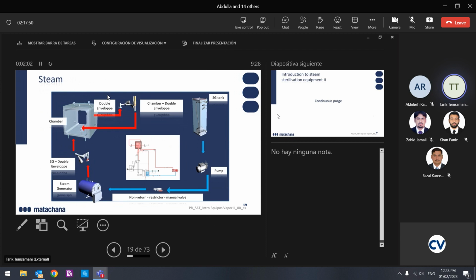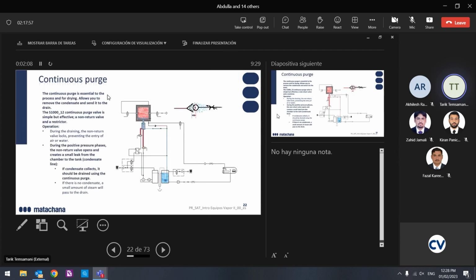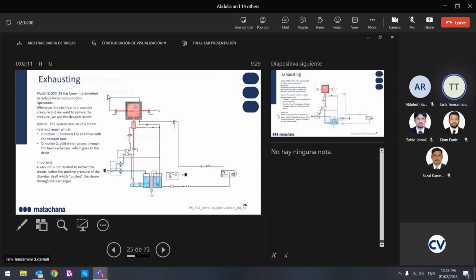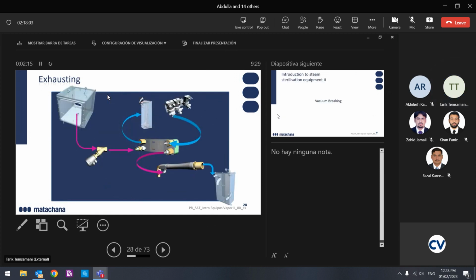But from the other side, we have the other line. I will explain better. Look, everything is explained here. This is the heat exchanger. Water valve, soft water: from one side we put cold water, and from the other side the line coming from the chamber after the sterilization. This line is hot and this line is cold, but when these two lines are mixed, we make this line colder. We can put it to the vacuum circuit without any problems.